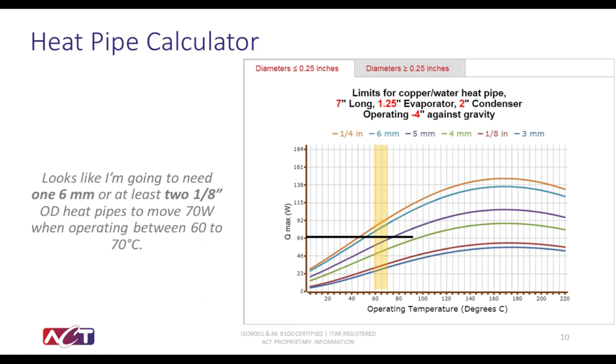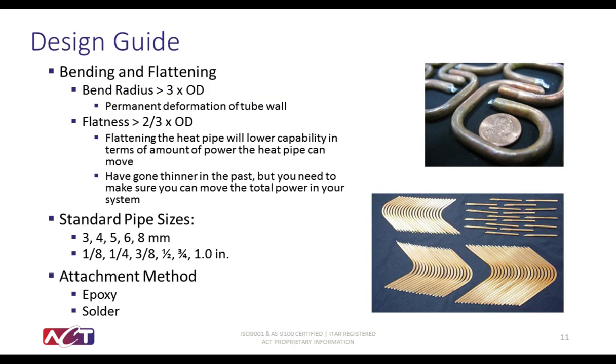So you've determined how much power you need to move, and now you understand what type of diameter heat pipe you need. Next, let's talk about how you can design that heat pipe into your next level assembly. Heat pipes can be bent and flattened, which aids in their ability to fit within your application. We recommend a minimum bend radius of 3 times the outer diameter of the heat pipe. For instance, in our past example, where you had a 6 millimeter OD heat pipe, we would recommend a minimum bend radius of 18 millimeters.